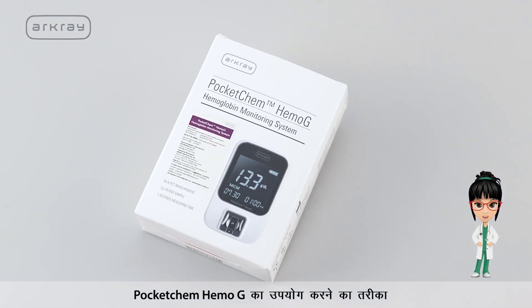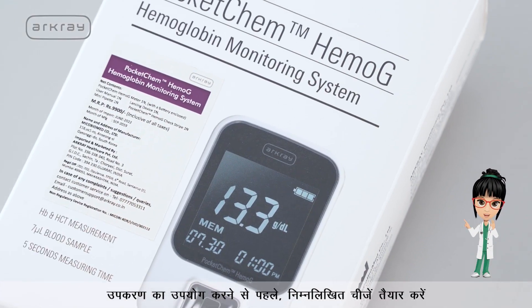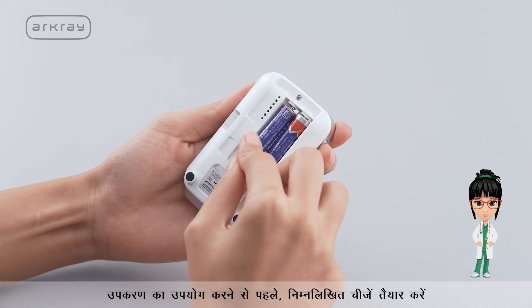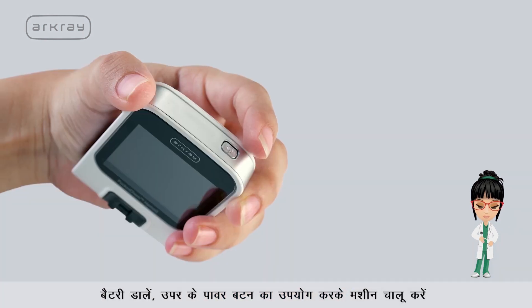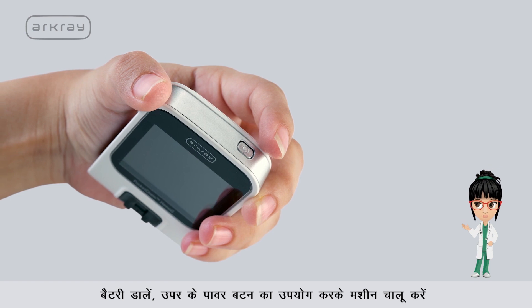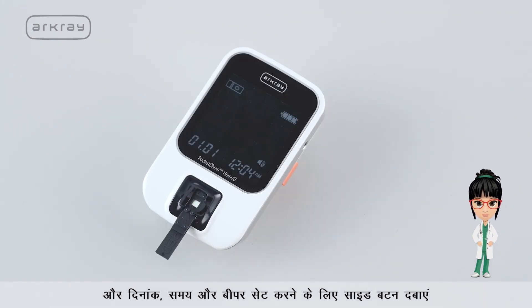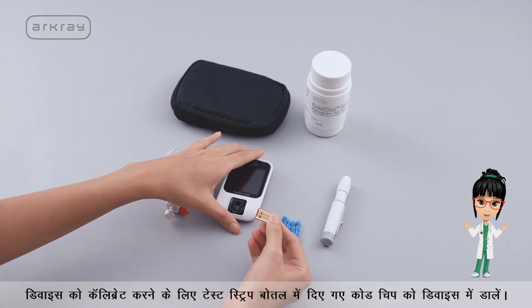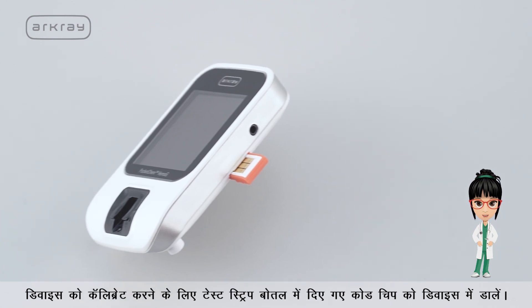Here's how to use PocketChem HemoG. Before using the instrument for the first time, prepare the following things: insert the battery, switch on the machine using the upper power button, press the side button to set the date, time, and beeper. Then calibrate the device by inserting the code chip given in the test strip bottle.